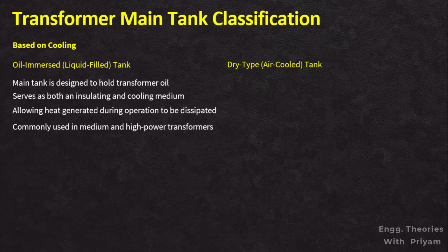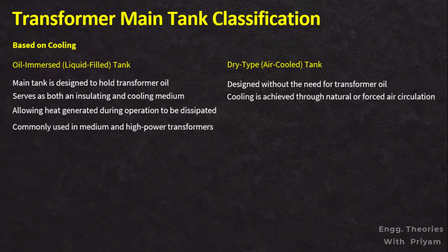Dry type or air cooled tank. In the dry type transformer, the main tank is designed without the need for transformer oil. The cooling is achieved through natural and forced air circulation around the core and the windings. The dry type tanks are often used in applications where environmental concerns, fire safety, and maintenance considerations make oil immersed transformers impractical. Forced oil cooled tank.